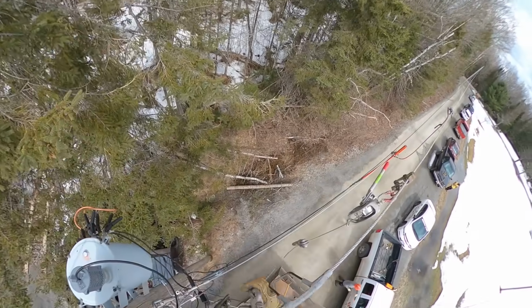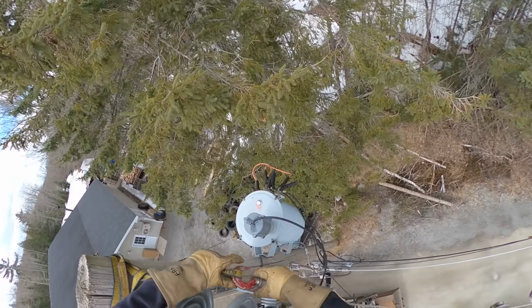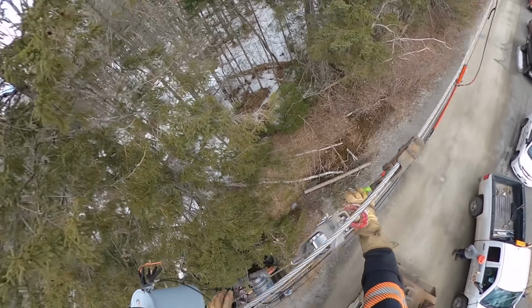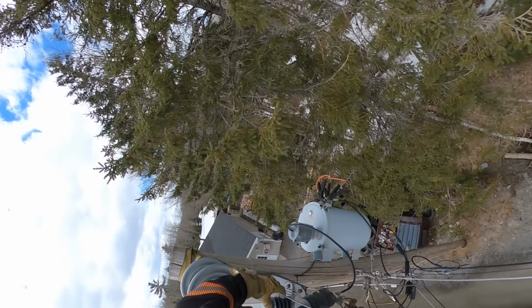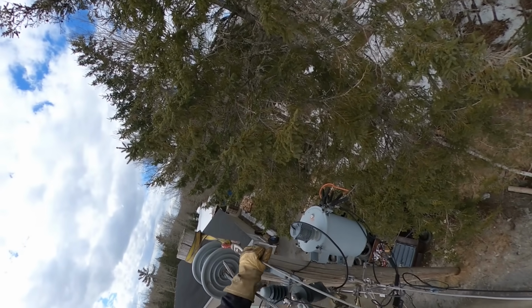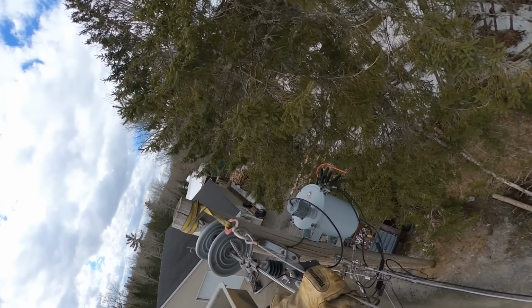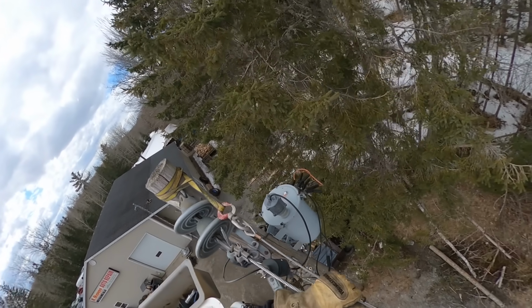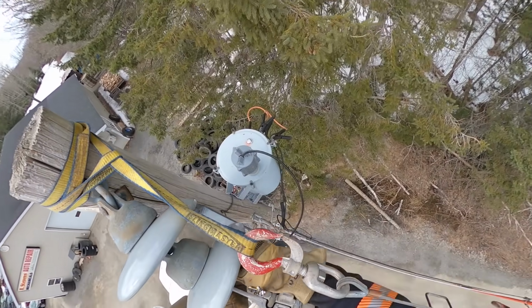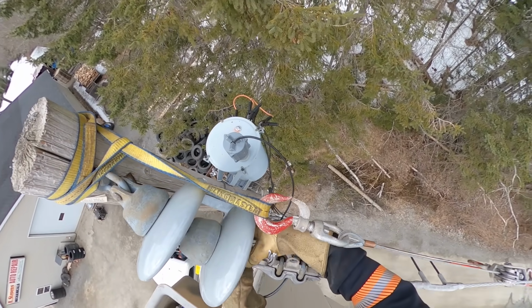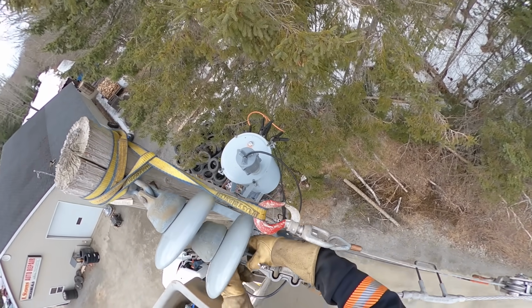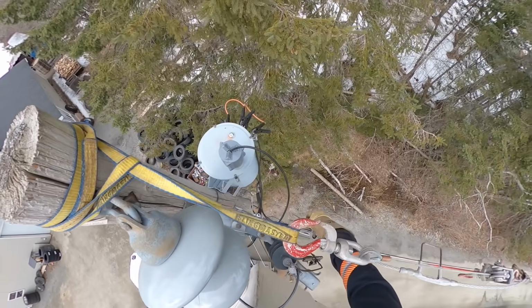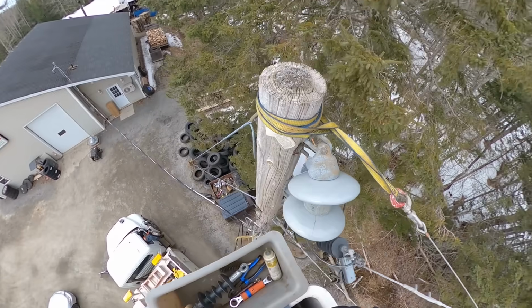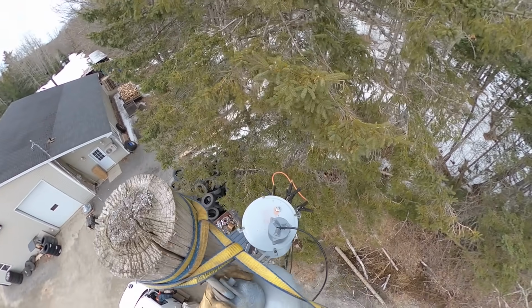Now we're going to change out those bells. So you notice I use a nylon strap, as opposed to wrapping my puller cable around the pole. If you wrap your steel cable around the pole and get in that habit, it's going to kink your cable and ruin them. And those come-alongs are like $600 a pop. You also want to have your strap coming straight off the pole. You don't want to have the knot and that bent back over the knot. That will reduce the strength of the strap significantly.